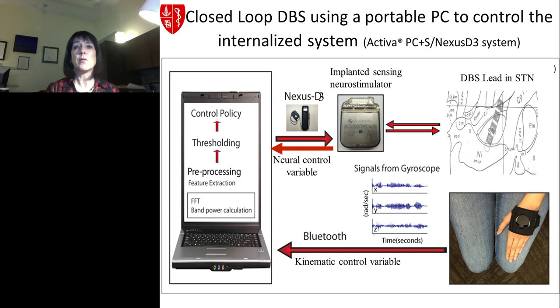And we can record from this lead, and the recordings, the local field potentials, can then be downloaded from the INS onto a tablet and then onto a PC via a bidirectional Bluetooth-enabled conduit called Nexus D3. On the PC, we can program the classifier algorithms, meaning what is sensed, and the control policy algorithms, meaning what is sent to the INS as the stimulation parameters, which is then sent back to the brain.